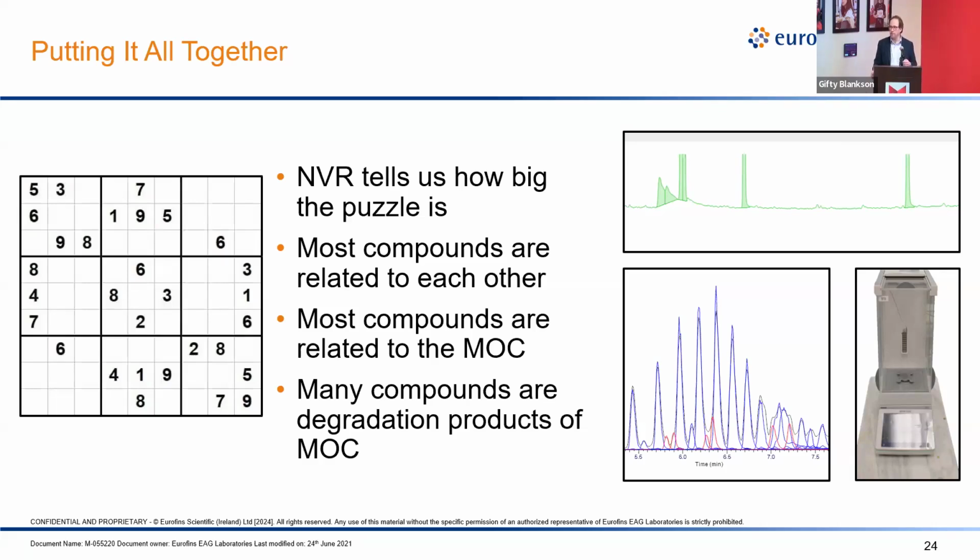Materials of construction, a lot of it. What is the device made out of? We'll see a ton of stuff from that. Polymeric device, I promise we'll see something that indicates what type of polymer it is. Even though it shouldn't be soluble, we'll see a little bit. But then there are also things like processing aids and surfactants. So hopefully at the medical device factory, they're cleaning, and they do a really good job, but occasionally you will see traces of surfactants. And it's fine. They're pretty much everywhere, ubiquitous, but we do see those. And FDA asks, okay, you saw it, how much was there, what is it? And what's the risk assessment? Is this going to be a problem or not in a person?